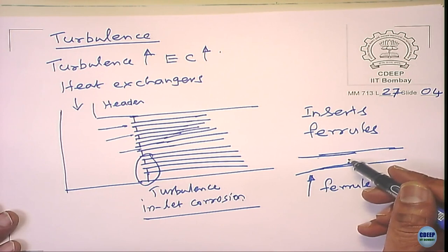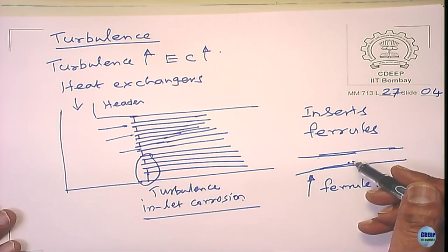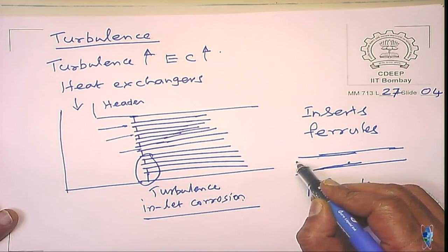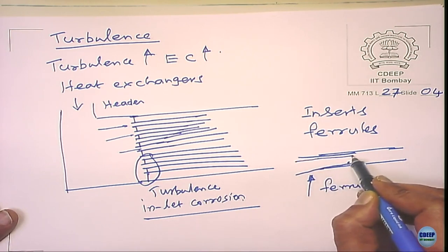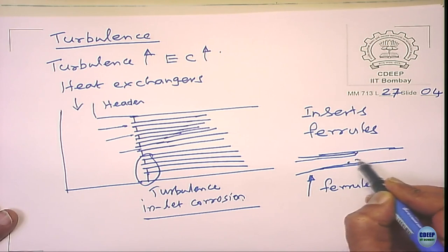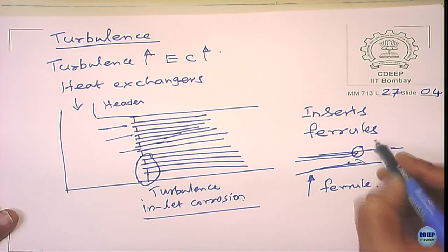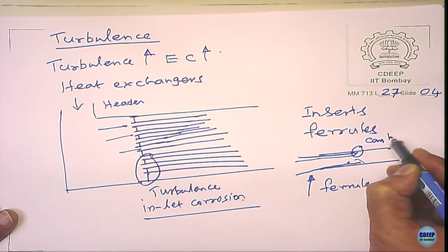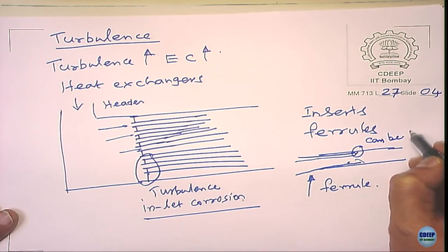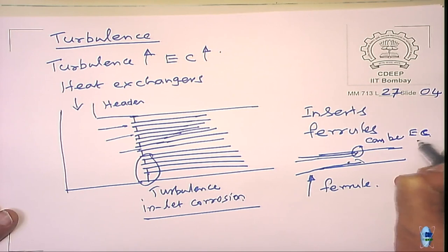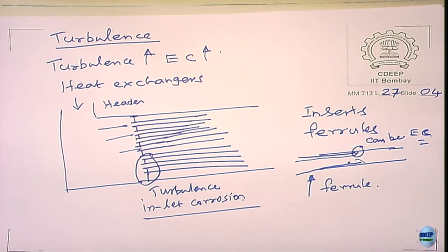But there is still a problem. When the fluid or liquid enters here, there is going to be a small step. So there can be erosion corrosion here. So you need to smoothen it out, make it like a feathery kind of tapering off, in order to reduce this erosion corrosion.